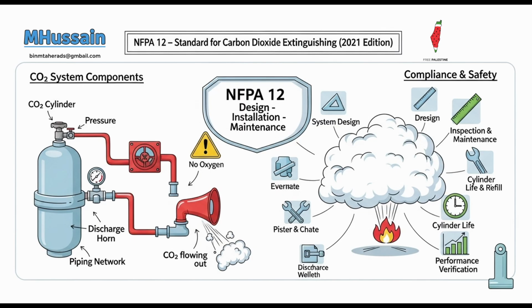So, with that essential foundation laid, let's finally get into the star of our show, carbon dioxide. CO2 itself. What is CO2 as a fire suppressant, and how does it actually work its magic to put out a blaze? What's fascinating here are the inherent properties of carbon dioxide that make it such a formidable fire extinguishing agent. First, it's a colorless, odorless, electrically non-conductive, and inert gas. Inert, non-conductive, key properties. Very key. This means it won't add fuel to the fire, conduct dangerous electricity, or leave behind any unpleasant smells or residues after discharge, a huge benefit for sensitive equipment. No cleanup, basically. Pretty much. It's also approximately 1.5 times heavier than air, which is a key physical property for its distribution. Okay, so it settles. It tends to displace air downwards, yes.